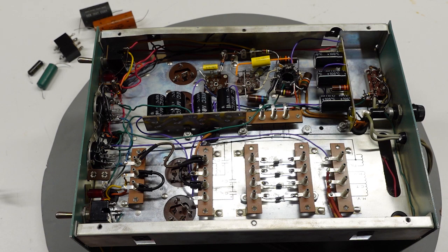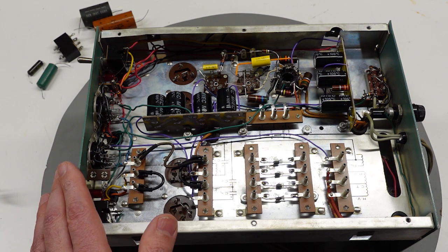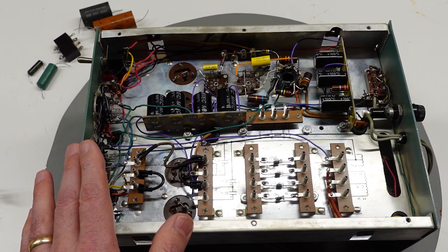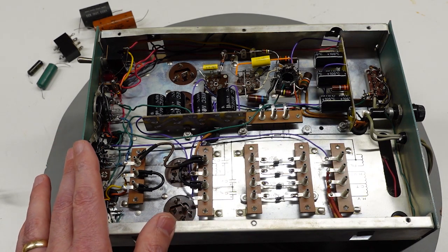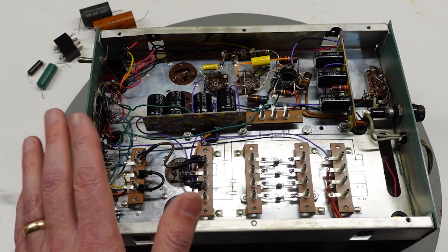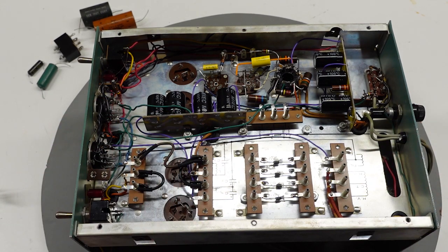And just for interest, in this case, I wanted to see, were all these caps bad? And there's a total of 10 of them, I believe, in here. No, I'm sorry, there are 9. And I checked them all, and only one of them is good by the standards of that tester. Good meaning it goes through and lights up the green light at a total amount of time similar to a new capacitor. So it means it has leakage that's similar to a new capacitor. Only C6, that's the .01 film cap, checked out good. All the rest of them were horrible. So confirmed what was probably an obvious expectation, that the caps were just beyond their lifetime. And now there are new ones in here, so all good to go.